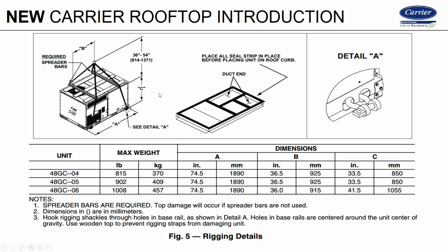Anytime, and this goes for any of our rooftops, the little 3 through 12.5 ton rooftops, all the way up to 150 ton rooftops, when you set these rooftops on a curb, your air side of the unit needs to be tight against the base rail. So if there's any extra play, that extra play needs to overhang over here on the condenser side. I've seen many units over the years where the rooftop was pushed this way, so the condenser side was tight against the curb, and now I've got a 2 or 3 inch gap over here that the air side's hanging over.